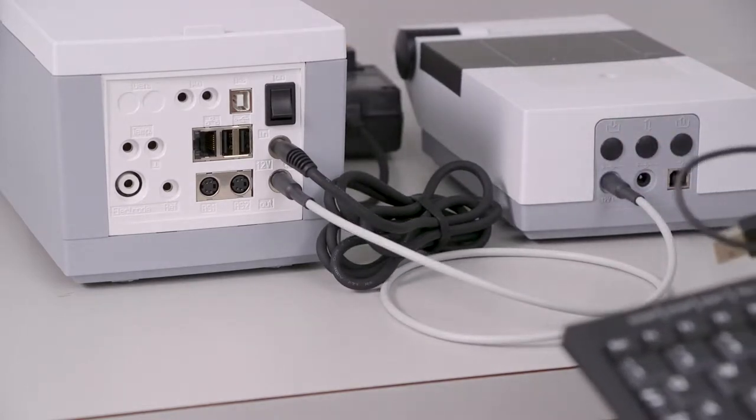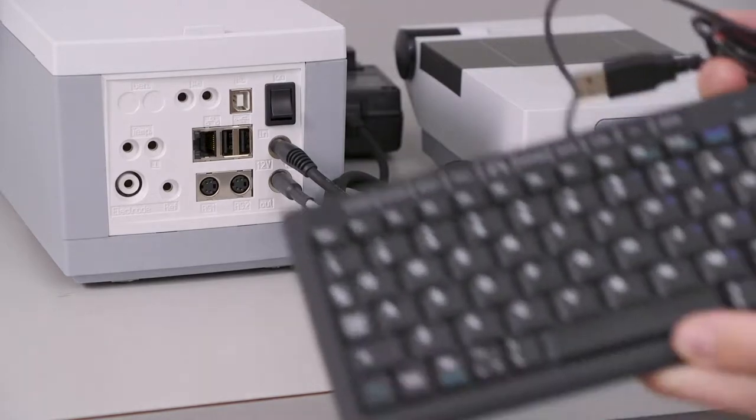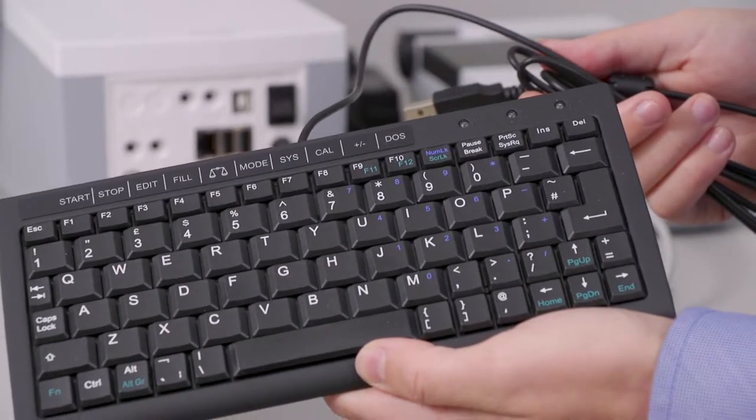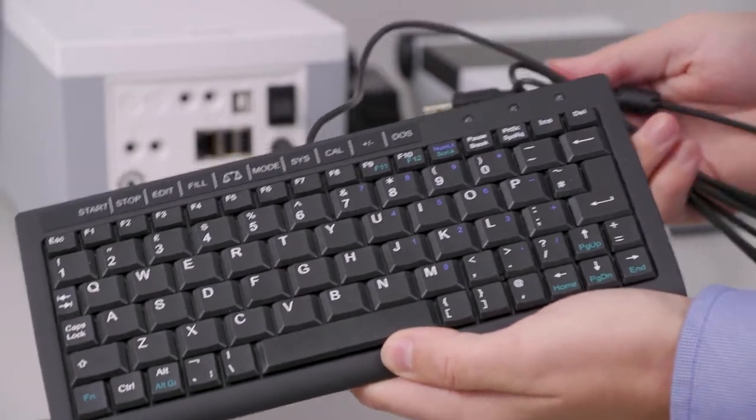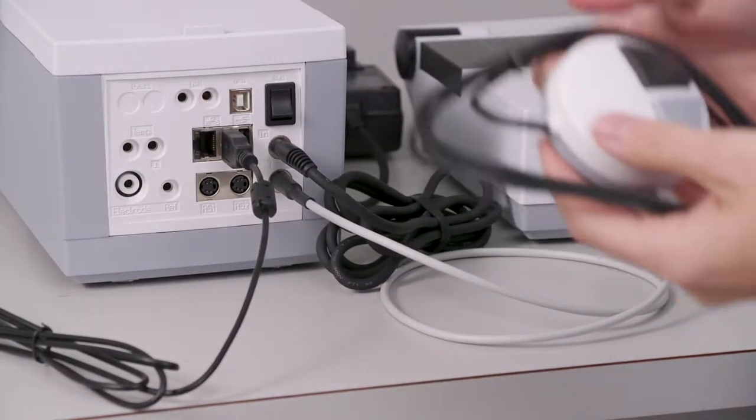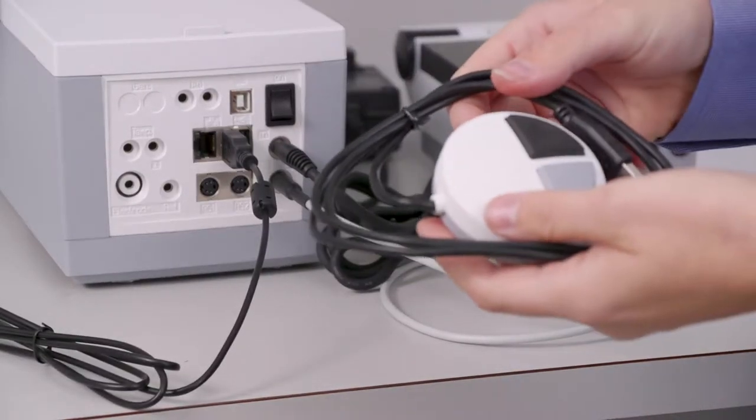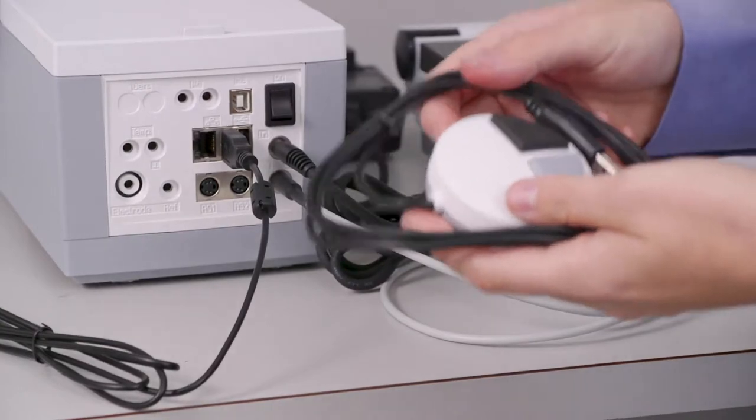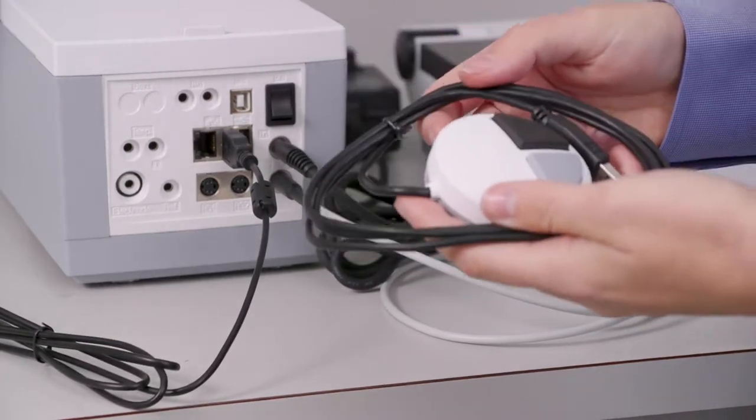Now is a good time to plug in any USB devices that you may have. One example is the mini keyboard that comes with all of our titrators. You can plug this into any of the USB ports that we have. A manual controlled mouse also comes with all of our units, but in this case we're going to skip it because we're running auto-titrations.